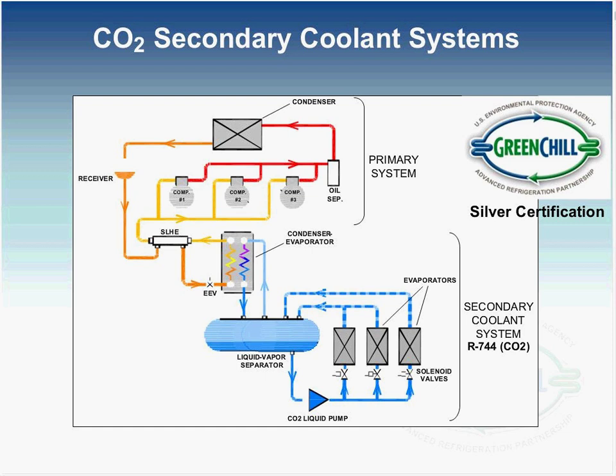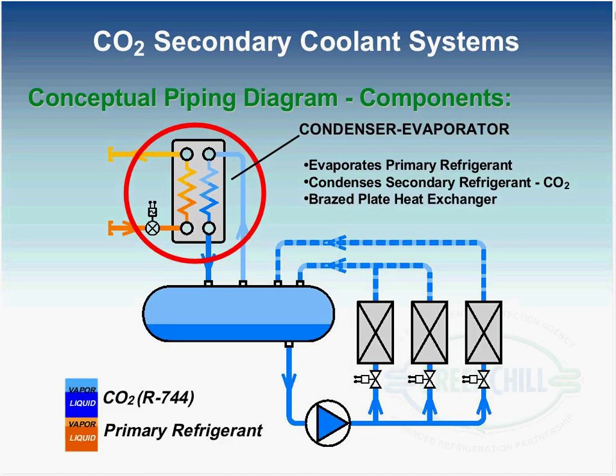Depending on what you do with your condenser and your heat reclaim, and I want to caution that you could get even higher certification if you use water cooled condensers or an integrated heat reclaim system. Starting out with that heat exchanger first, that is the condenser evaporator. It's an evaporator on the HFC side, on the primary refrigerant side, and it's a condenser on the CO2 side. So on the right-hand side there, we have the CO2 condensing into a liquid. It's a brazed plate heat exchanger, so a lot of reliability in the system there.